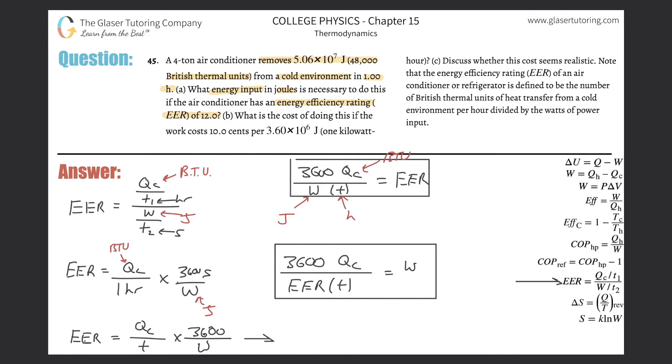Now, all you got to do is plug the stuff in. So, this is 3,600, multiplied by Q sub C in BTU, so that's 48,000, divided by the EER value, and that was 12, multiplied by the time in hours, which was one hour, and that's it.